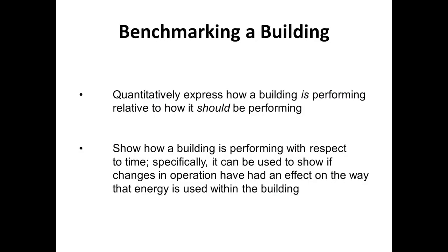So the first thing is benchmarking a building. The purpose of benchmarking a building is to quantitatively express how a building is performing relative to how it should be performing. Using tools such as Portfolio Manager, we're really going to rate a building on a scale of 1 to 100, with 50 being average, and see if the building stacks up to its peers in its peer group, meaning buildings of similar size and operation. And then also show how a building benchmarked against itself, how it performs 1 year compared to the next or 1 month compared to the next. It's helpful to track energy usage over time for a building and look at, whether it's 2010 or 2011, how a building improved, how a building may have handled the heating season or cooling season or base period, and seeing how that can be improved from year to year.